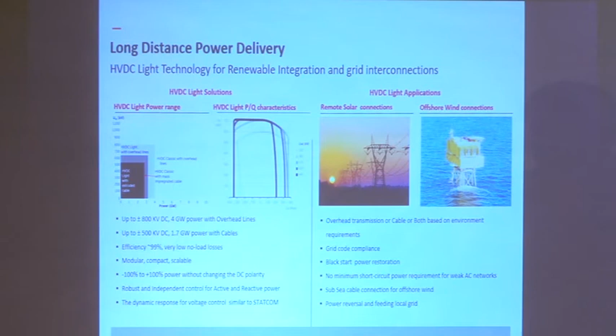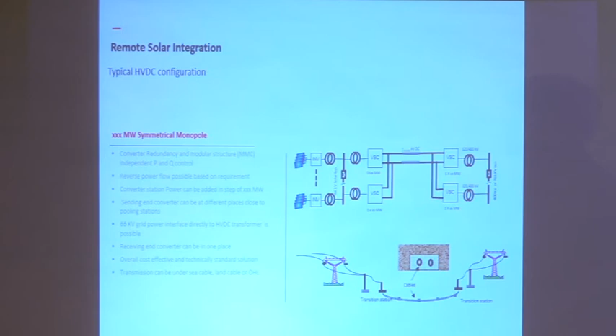This is a typical diagram of an HVDC connection, which we could see either from Oman to India or from any place to any place using cable, or a bigger one using a transmission line. Here we have a big solar plant connected through inverters and transformers at 66 kV level. The power is pooled at 66 kV, then connected to the HVDC transformer, which connects with the HVDC voltage. Then HVDC takes the whole power to the recipient station in a manner that it would look as good as a generating plant at the load center.